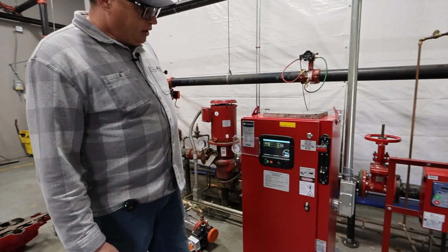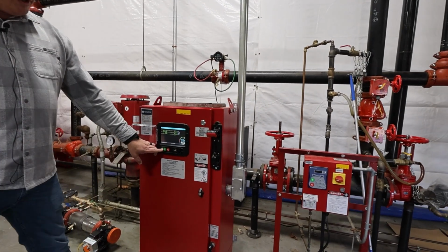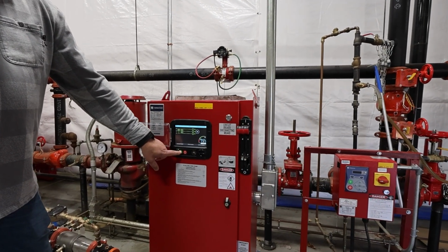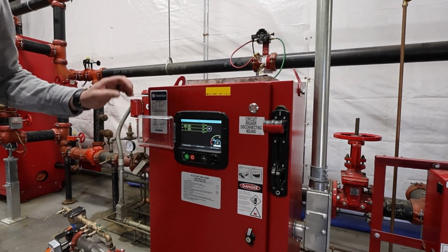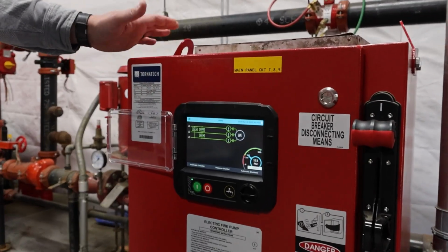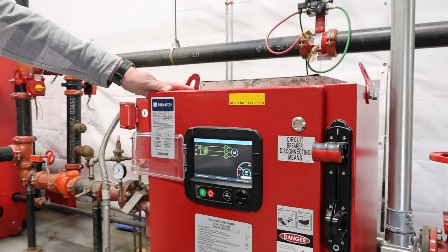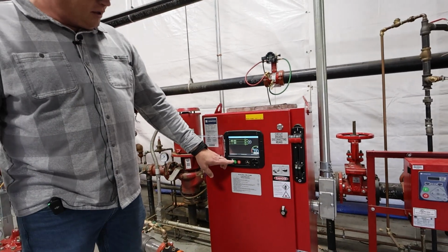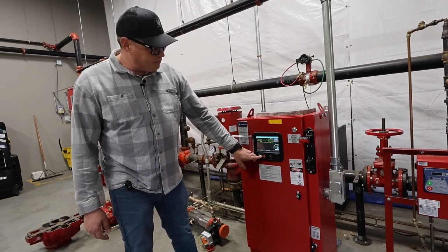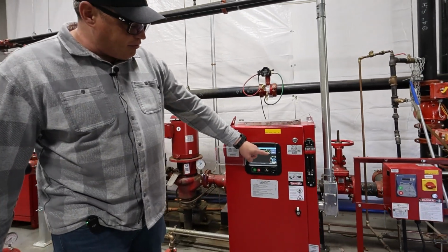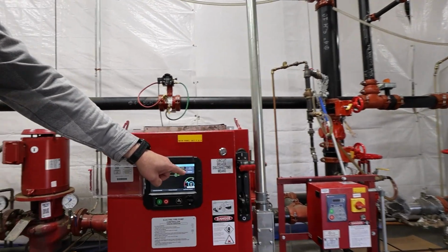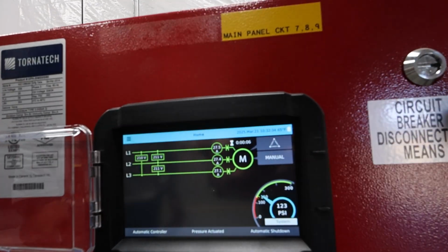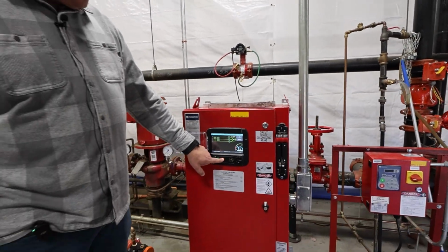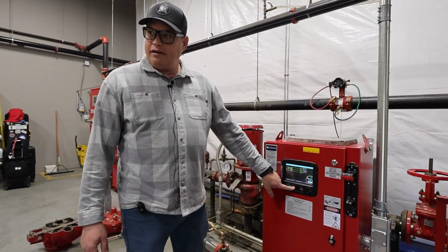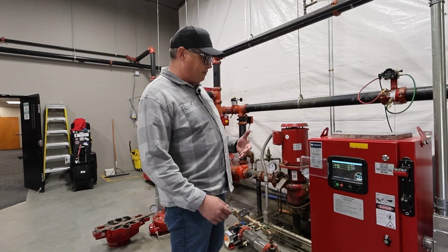Right, yep. So we'll go ahead and hit start real quick just to show you what happens when you start a fire pump. This one in particular is across the line. This is a 20 horsepower Tornatech GPA. And we'll go ahead and hit start. So you can see right here on the screen that it was started in manual. Yep. And now we'll go ahead and shut it off.